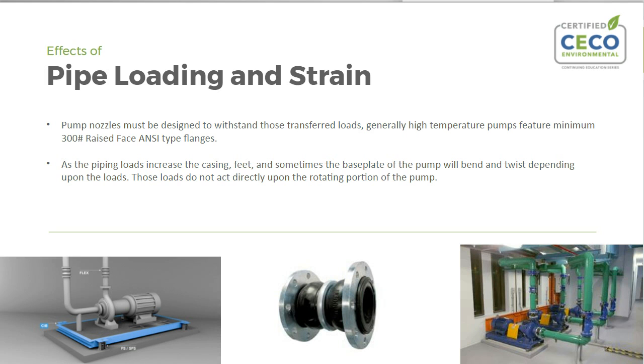Once again, at some point, this pump has to be connected to the piping itself, and the piping was not installed at high temperature. It was installed at ambient temperature. The pump was installed at ambient temperature. And so these loads and strains, once that piping starts to actually increase in temperature and heat up, it can cause tremendous expansions and contractions depending upon how long the piping is and how many twists and turns it has to make before it actually gets to the pump itself. So the nozzles of the pump must be made to withstand a certain level of pipe loading, a certain level of stress imparted to the pump from the piping itself.